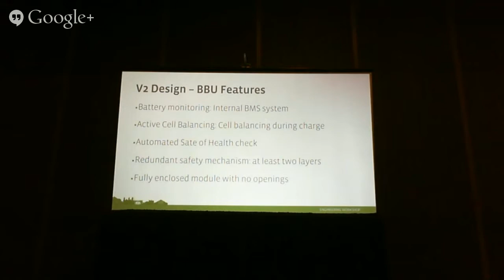We have redundant safety mechanisms. Safety is very important, so we've introduced at least 2 layers of safety that are completely independent of each other. A safety mechanism can fail, and you have a backup for it. The fact that we're going through the power supply creates a sort of free safety mechanism for us, because the power supply is monitoring the BBU and knows its state, so it can cut off access to the BBU if there are failures.